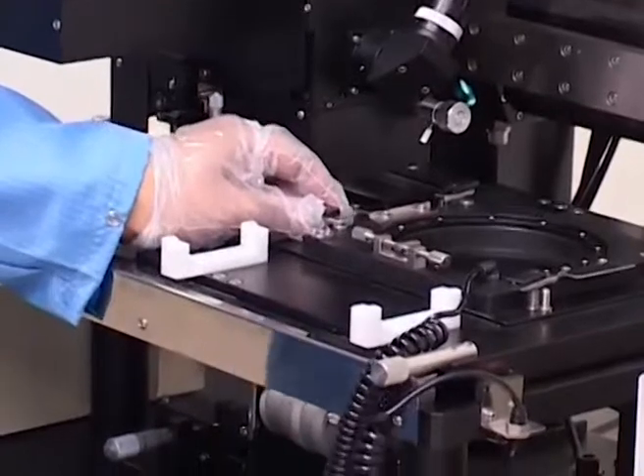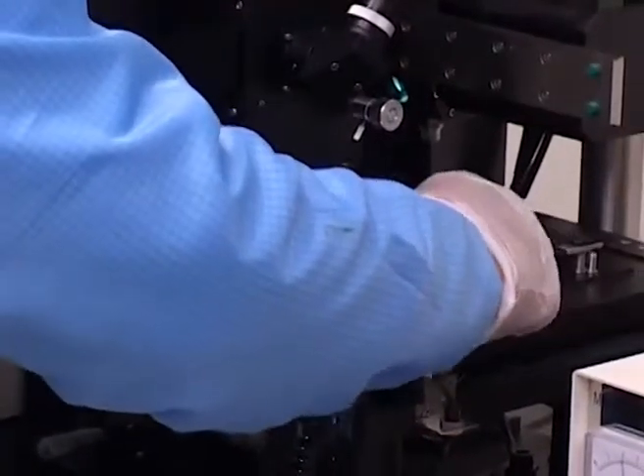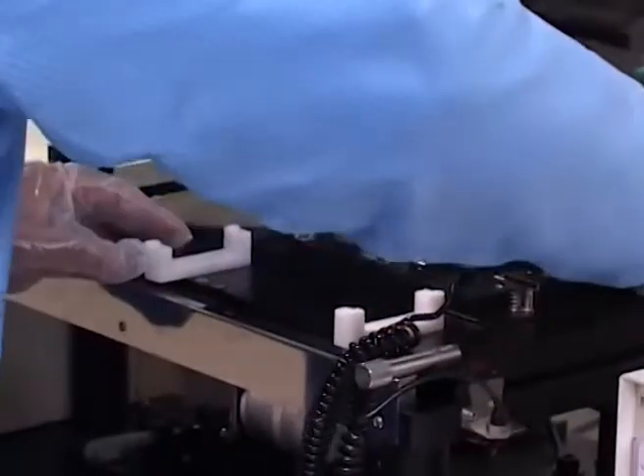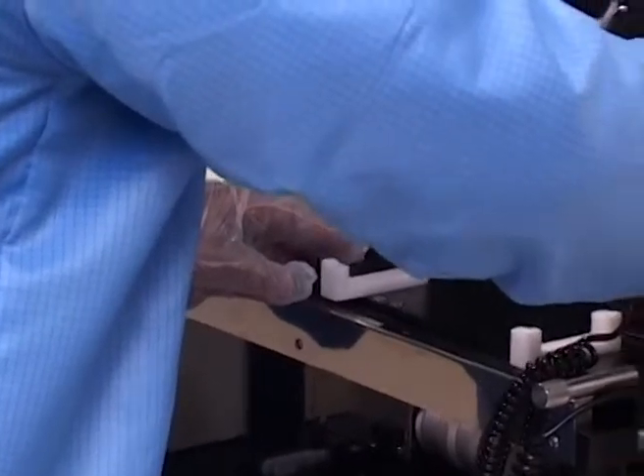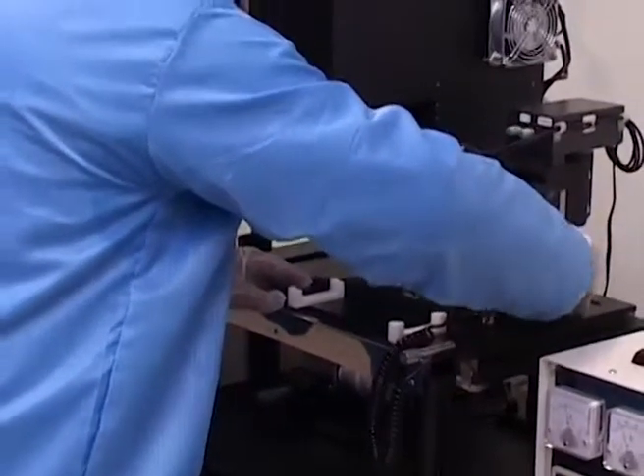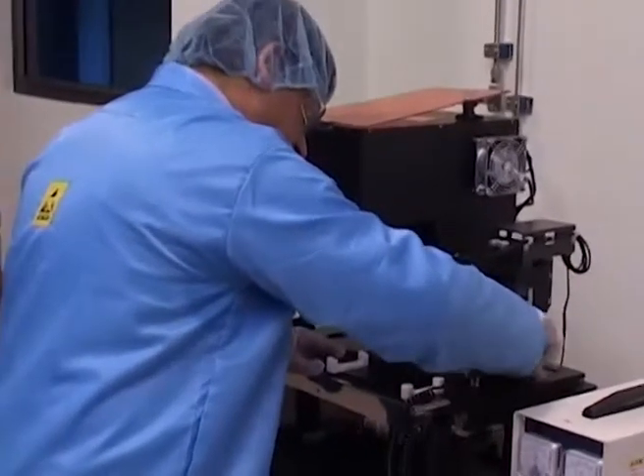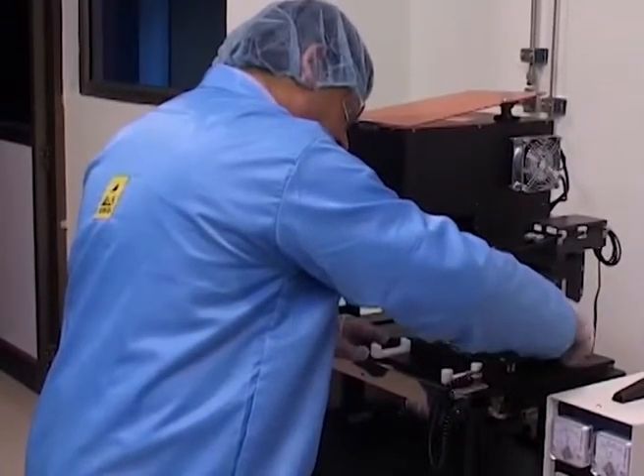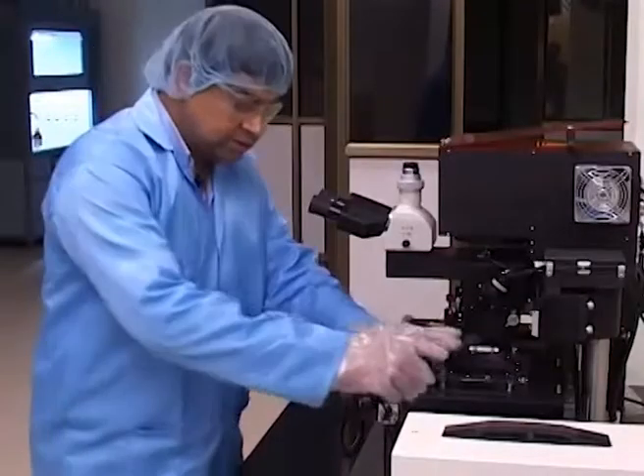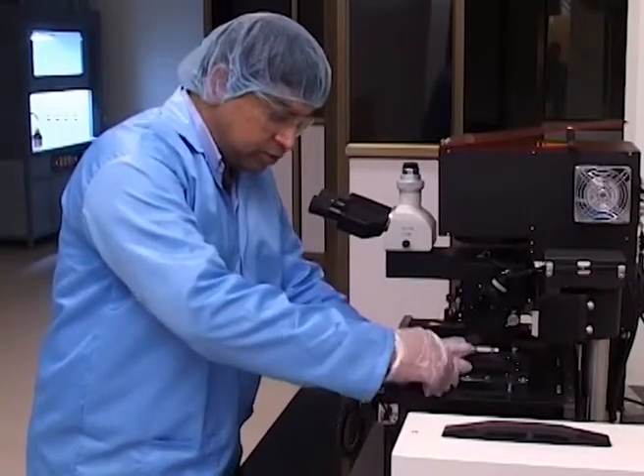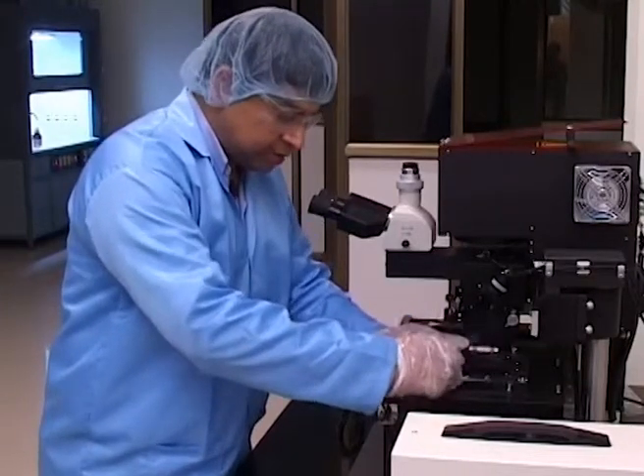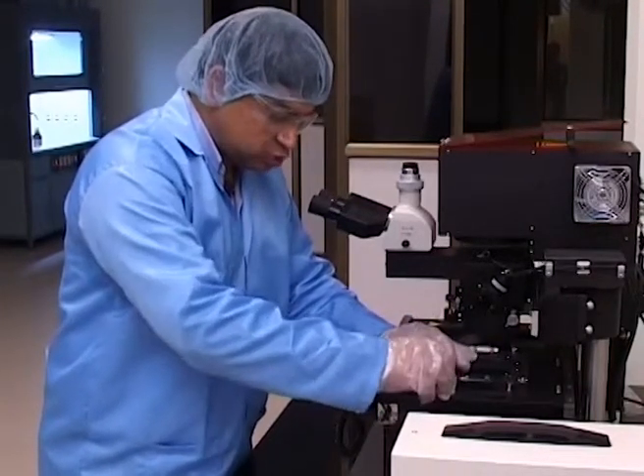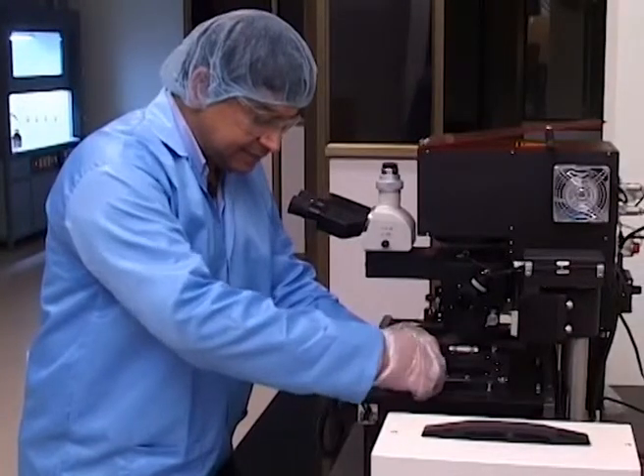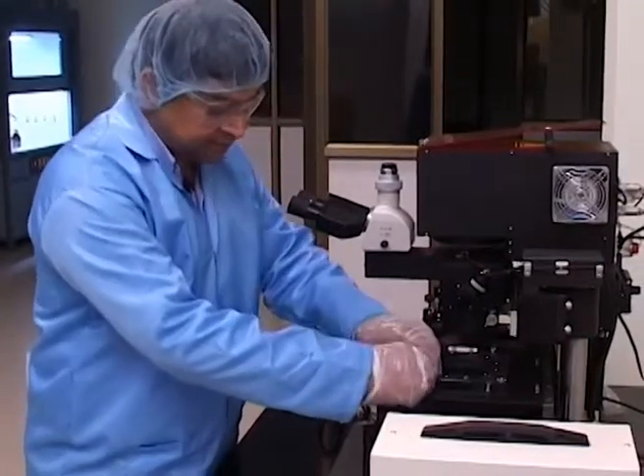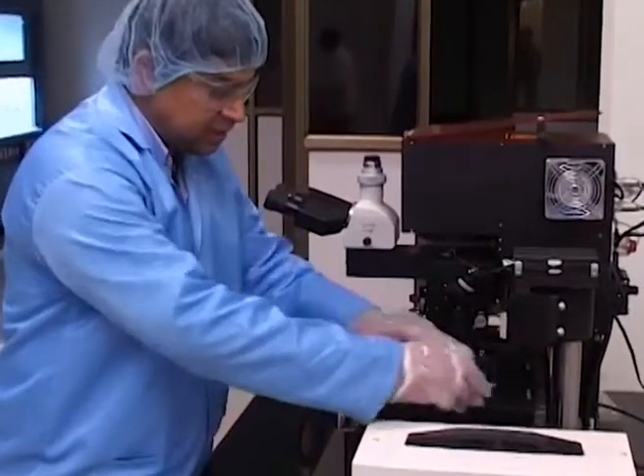There are four bolts for that purpose. You try to align them with the bolt heads which are on the top of the mask holder, and essentially you can now use the locking mechanism to ensure that they firmly get locked over the wafer surface. After mounting this properly, we need to bolt it firmly. So we are going to use these set of screw heads to ensure that there is a good contact between the holder and it grips really well on the surface.